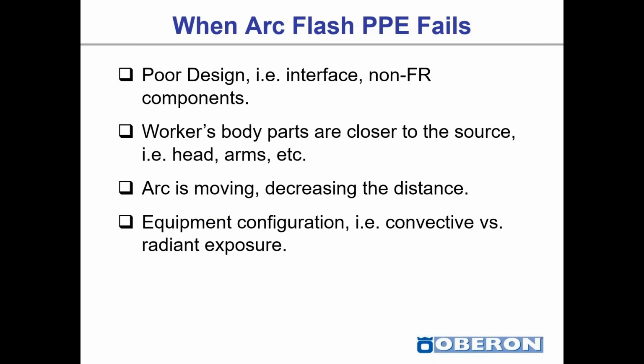When arc flash PPE fails, examples would be poor design, specifically the interface, the non-FR components that could be used in the manufacturing process by some manufacturers out there that don't understand the ASTM F1506 standard and how to use that standard in manufacturing products. Workers' body parts could be closer to the source, so your head, your arms, etc. We actually consider your arms and hands to be expendable because we're doing the calculations, or EasyPower would do the calculations, based on the distance from the arcing source to your chest and your face.